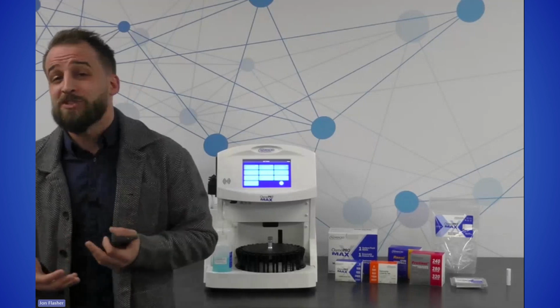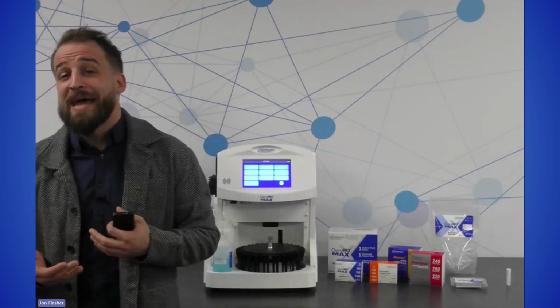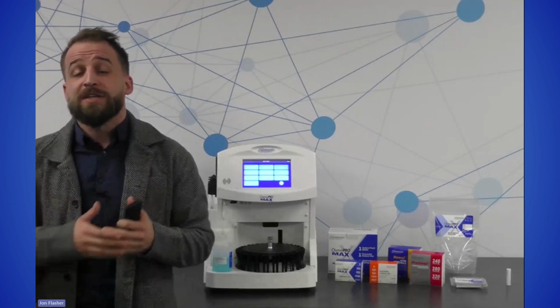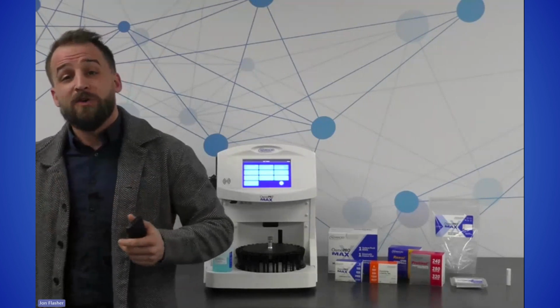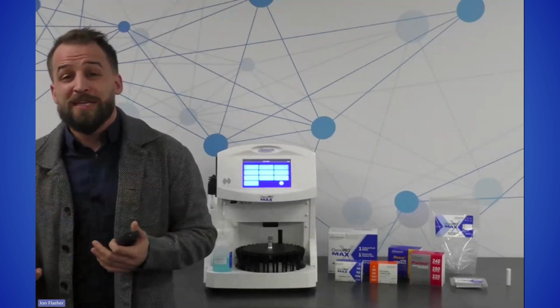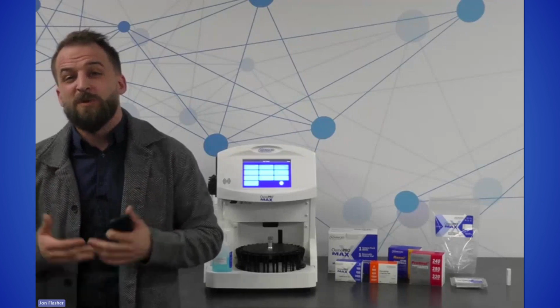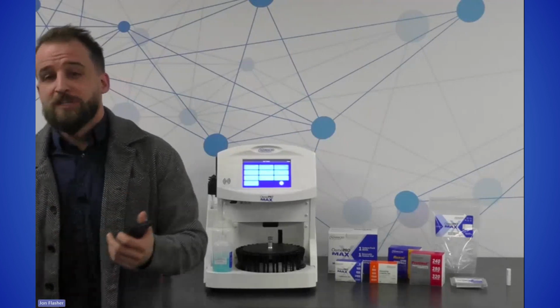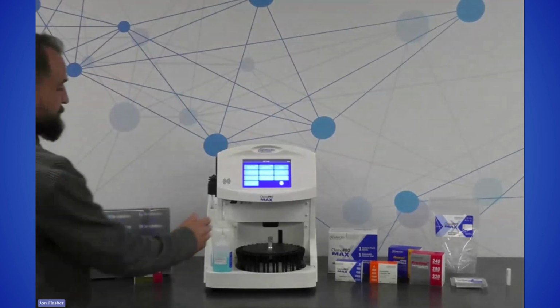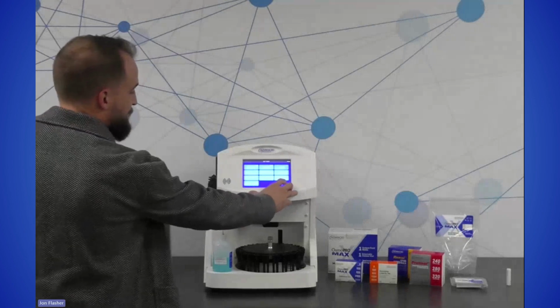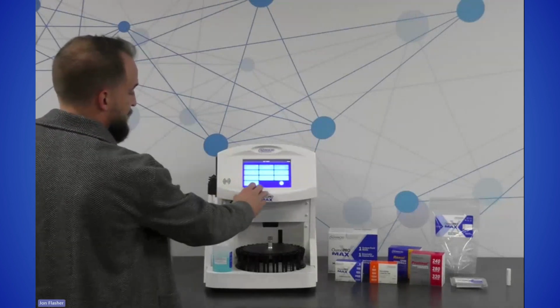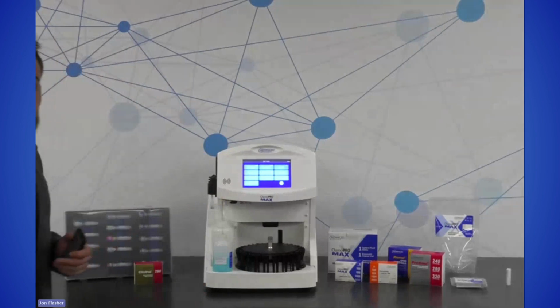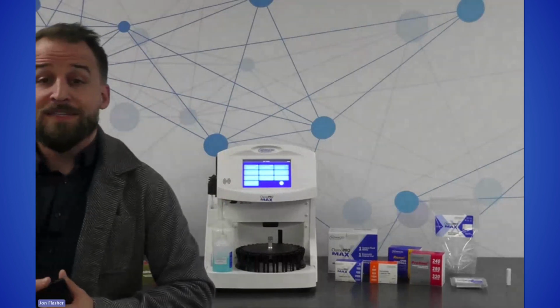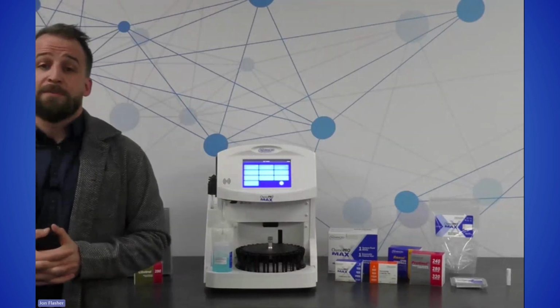So this is just a feature that we added as an extra level of assurance to ensure that you could consistently perform testing without any interruptions or without the frequent need to completely recalibrate the instrument when it isn't necessary. So just an added feature that we put in there to make sure that we could accommodate the continuous testing of osmolality. What's that? The daily Clinitrol 290 run is not optional, no.